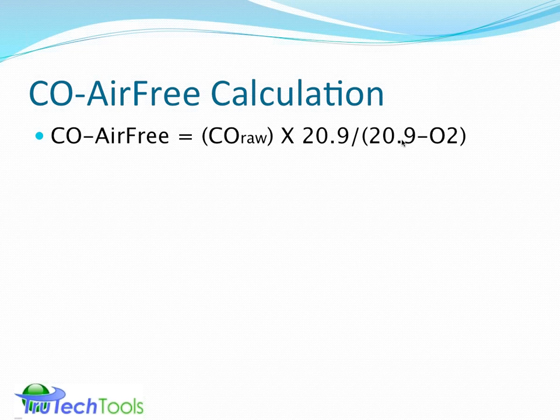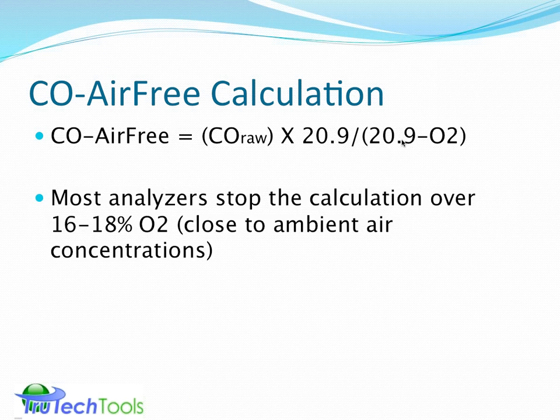You either have to have another oxygen meter or some way of measuring simultaneously and dynamically the same parameter, oxygen and CO at the same time. Usually this means you need a combustion analyzer because typically 80, 90, 95% of them contain CO and O2 sensors together.